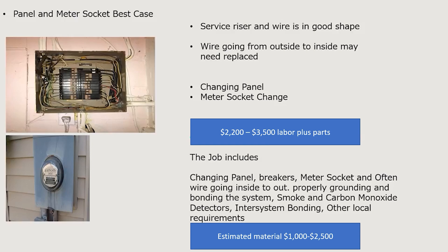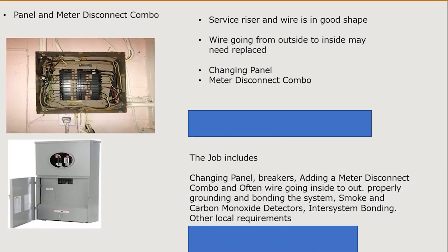Scenario three is the panel and meter disconnect combo — a very common scenario in the 2020 and 2023 code cycles because everything requires that emergency disconnect. We'll likely need to reconfigure the wire going into the home. We assume the service riser and wire outside are in good shape, though the wire from outside to inside may need to be replaced or a fourth wire added. This includes the panel change and installation of the meter disconnect combo. Estimated labor: $2,500 to $4,500. Estimated material: $1,500 to $3,000.